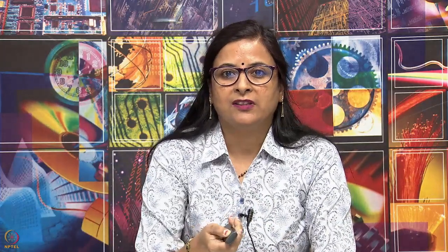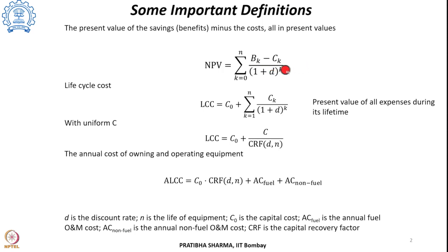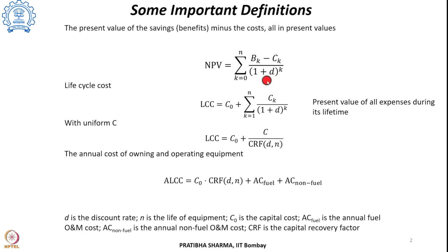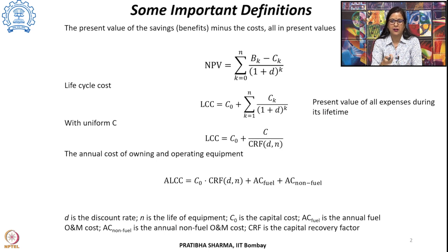In order to include the time value of money, there are other terms used, like net present value or life cycle cost. Net present value takes into account the savings minus the cost, with a discount rate in the denominator. The discount rate considers the time value of money — what an investment made today will be worth in the future. This is summed over the number of years: for the k-th year it is (B_k - C_k) / (1 + d)^k, where d is the discount rate and k is the year.